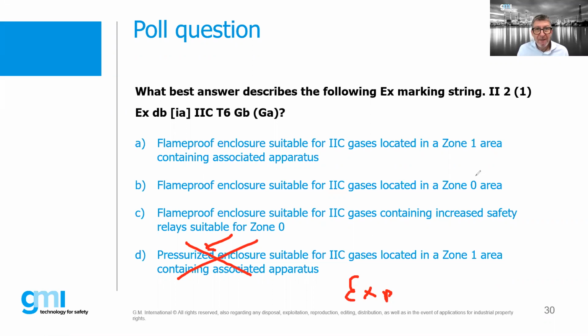There's also another giveaway, which is easy. We have parentheses. Bob earlier said that parentheses mean something. Yep, a second certification. In this case, it means that it contains, right, Bob? Yeah, a couple of giveaways here. It is definitely a flame-proof enclosure; we see the db, but we also see this ia in square brackets, and the ia tells us that the enclosure is containing an associated apparatus, meaning that in effect this is a flame-proof box that contains intrinsically safe barriers providing protection downstream into a Ga environment, which is zone 0, but it can only be mounted in a zone 1 area. So if we think about all our options, a flame-proof enclosure IIC located in zone 1 containing associated apparatus would actually be the correct answer.